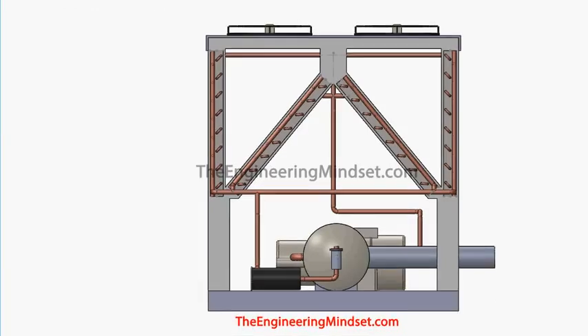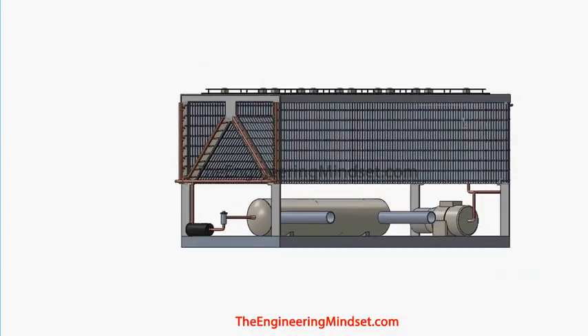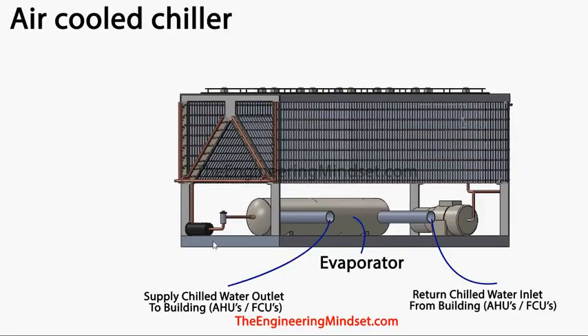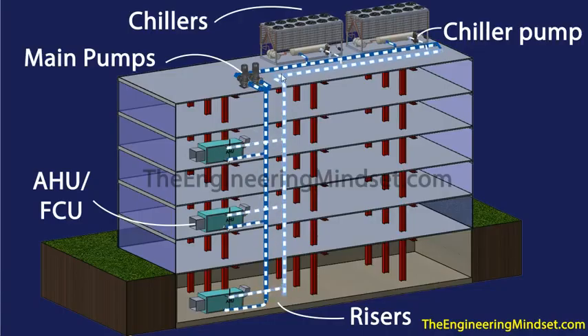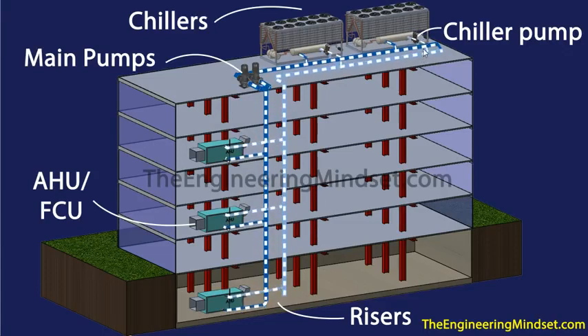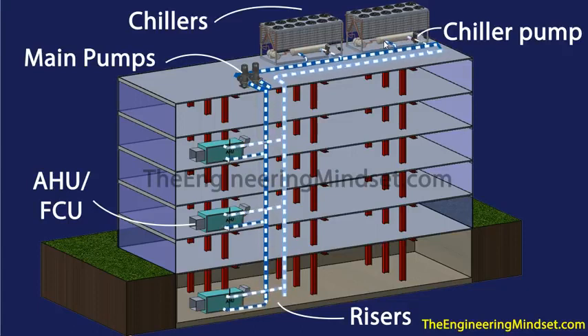So we just changed the view on this one as well. And from this one we can see that the refrigerant, after it's passed through the filter dryer and into the expansion valve, is then going to make its way and pass into the evaporator. So this big tank at the bottom, underneath all this stuff, this is the evaporator. This is where the return chilled water, if you remember this water just here, the return water, is going to enter, pass through the evaporator and make its way back out much cooler.